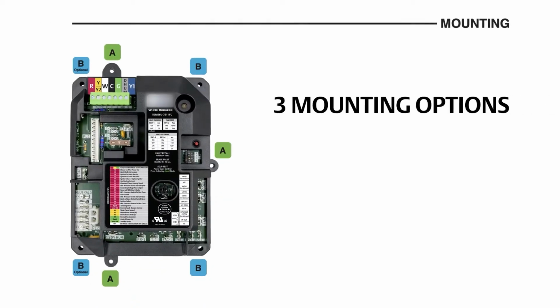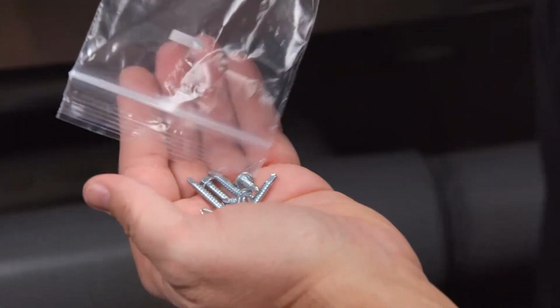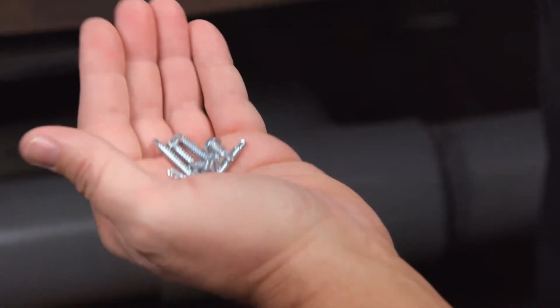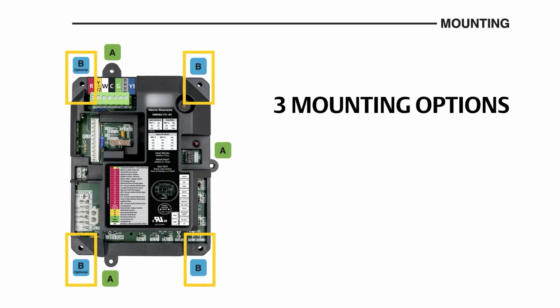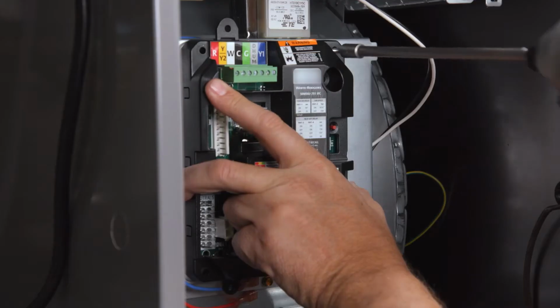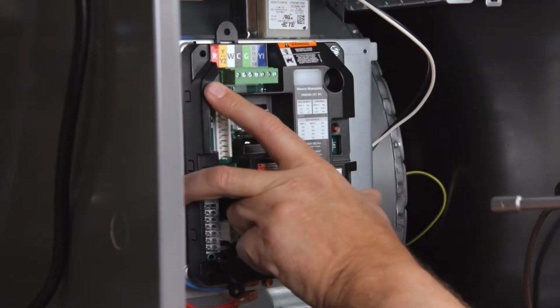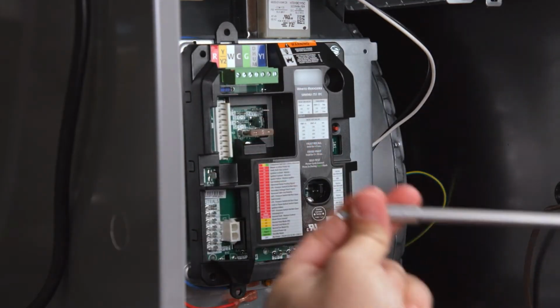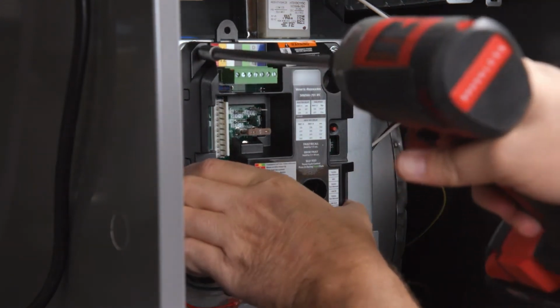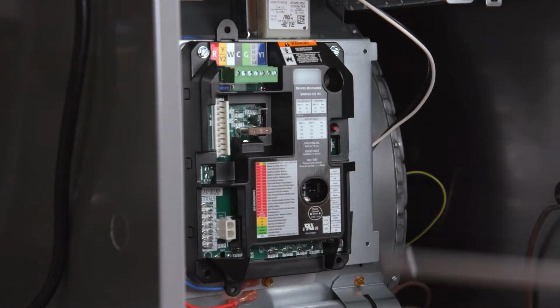The control can be mounted using one of the 3 mounting options noted in the mounting section of your instruction sheet. The tabs are used for OEM direct mounting when replacing controls with a tray. Secure using the 1/2-inch screw included in the kit. The corner holes are used for OEM direct mounting when replacing controls with metal standoffs. Align the right-hand side corner holes with factory sheet metal hole locations and secure with 1-inch screws. You may secure with 2 additional screws on the left-hand side.